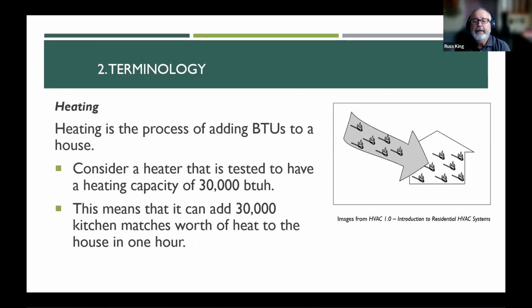Heating is the process of adding BTUs. So the load calc is calculating how many you're losing, and then you size your furnace, or your heat pump, or your heater, to add those BTUs back in at least the same rate. Okay, so a 30,000 BTU per hour furnace is adding 30,000 kitchen matches worth of heat in an hour. And again, whether that's big enough or not depends on your load calculation.